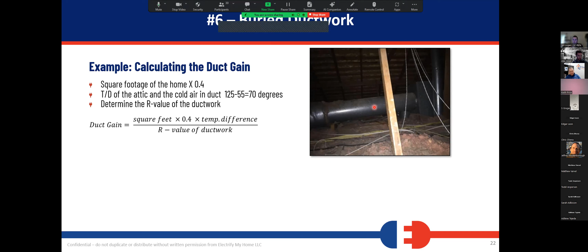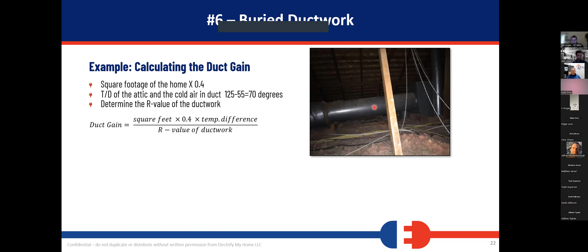But if we were to take all of that ductwork out and slice it down the middle and measure the inside of it, it comes to between 38 and 42% of the actual square footage. So what that means is, and we're going to use a nice easy number right in the middle of 0.4. So if I have a 1,000 square foot house, I'm going to have roughly 400 square feet of internal duct surface area. If I have a 1,500 square foot house, I'm going to have approximately 600 square feet of internal duct surface area. So we can do the math on this.